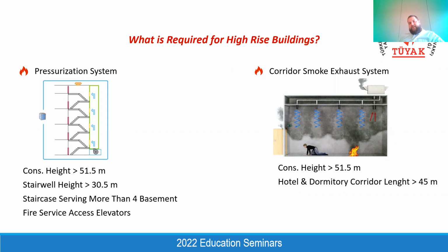And also for the high-rise building, if the construction height exceeds 51.5 meters, we also need to provide a corridor smoke exhaust system, and it requires great coordination between the architectural team and the mechanical team to find some vertical shafts, because for each corridor we need to provide 1 exhaust shaft and at least 2 separate makeup shafts. I will explain with all details. It's very important: if we are not coordinating it at the beginning of the project, and if we finalize the structural design, it becomes really impossible to find the required area of shafts for this corridor smoke exhaust system. It's also the responsibility of the architect to coordinate these shafts and the shaft locations within the high-rise building.